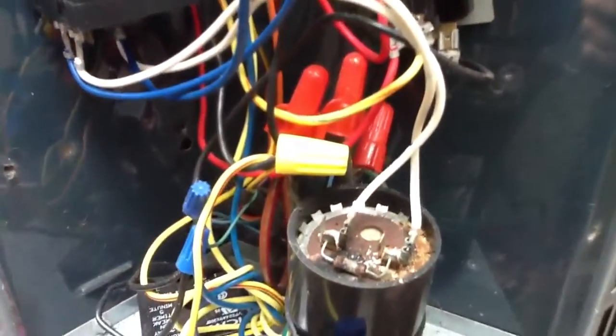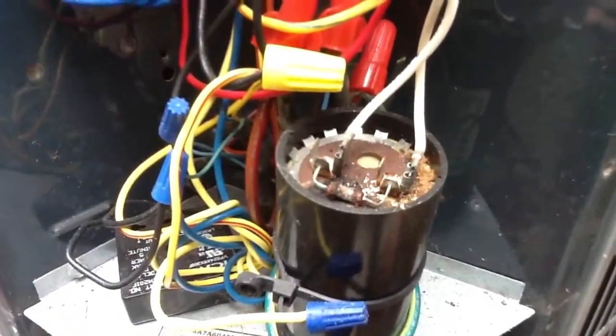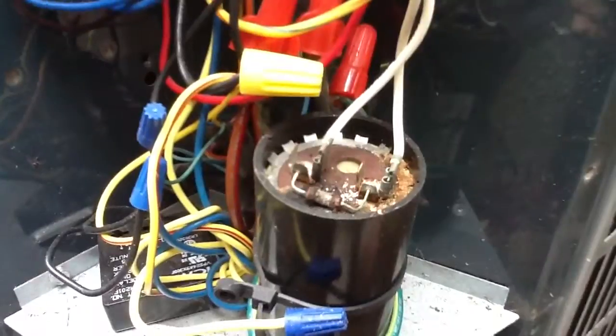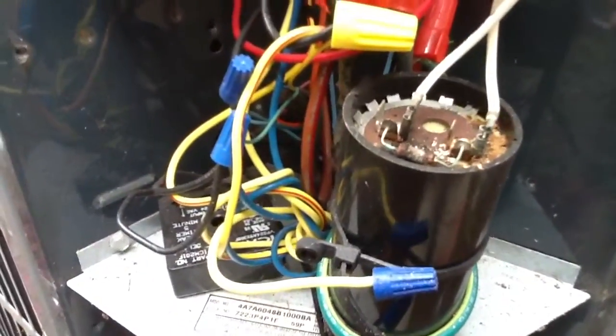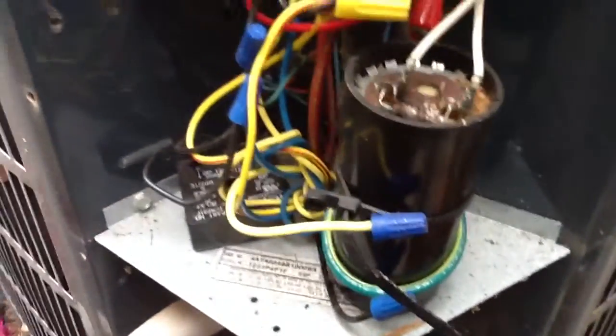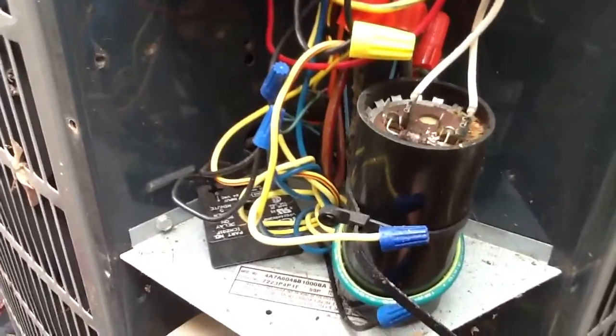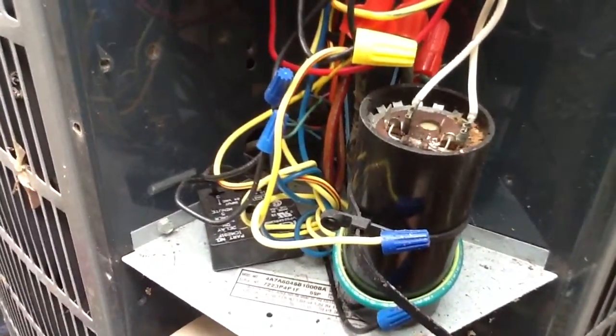But here's the culprit — it's the kick start on the unit. So the kick start will have to be replaced. And if you look to the left, that's a time delay. So what we're doing here, we're actually just reviewing the different components of the average condenser. You have there on the left-hand side on the bottom — that is a time delay.